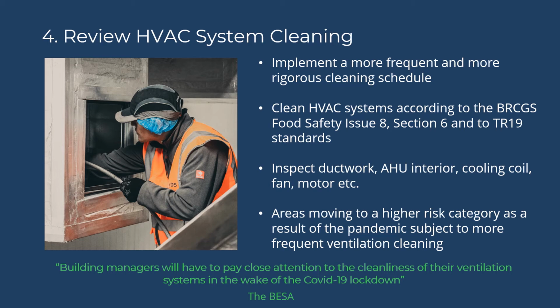We would like to point out that cleaning should be carried out in accordance with the BRCGS Food Safety Issue 8, Section 6, which gives guidance on best engineering practice with regard to the ongoing maintenance, condition, and hygiene monitoring of ventilation equipment. All parts of the air handling system should be inspected, including but not limited to cooling coils, fans, motors, and the sides, walls and floor of the air handling unit itself.